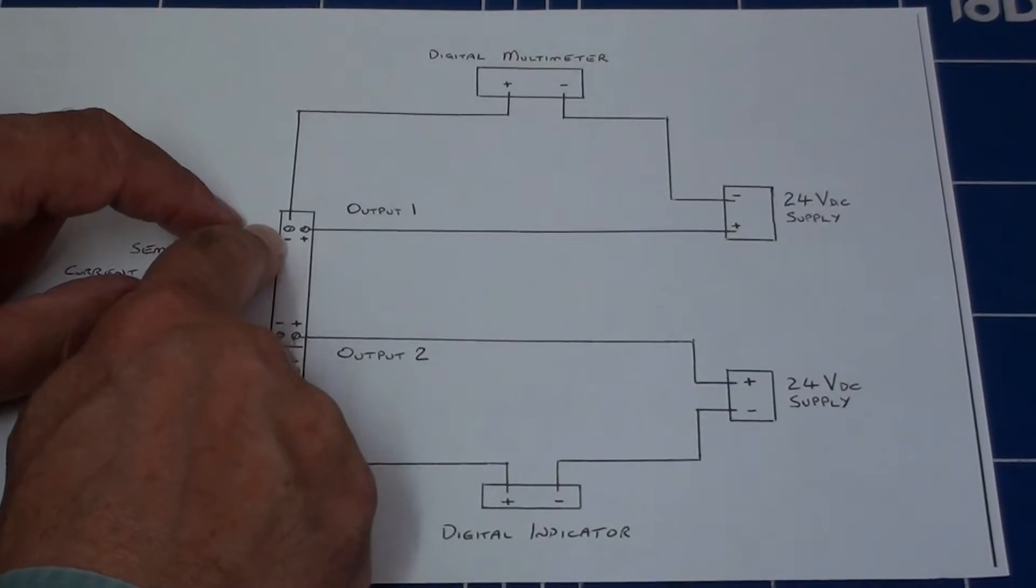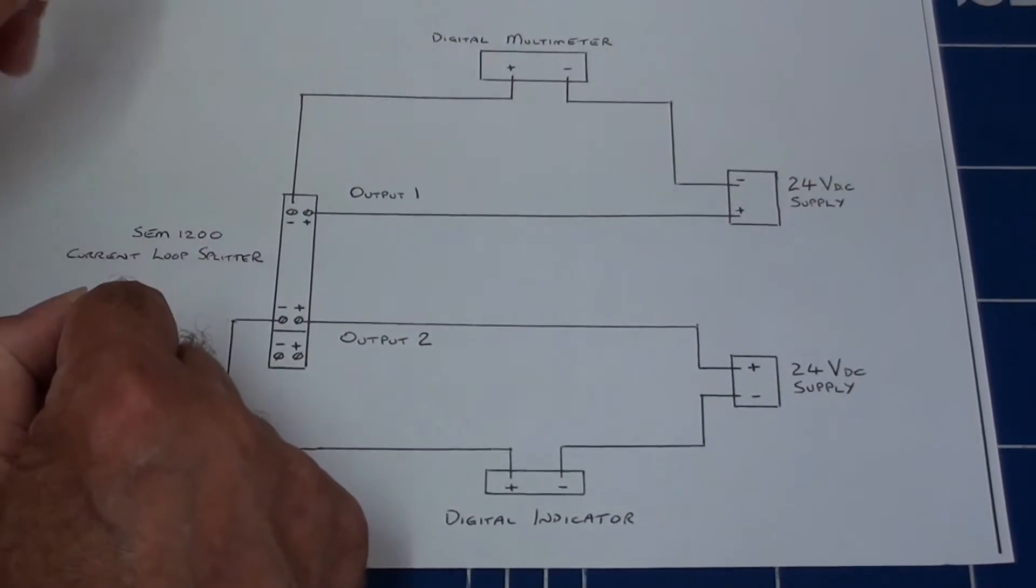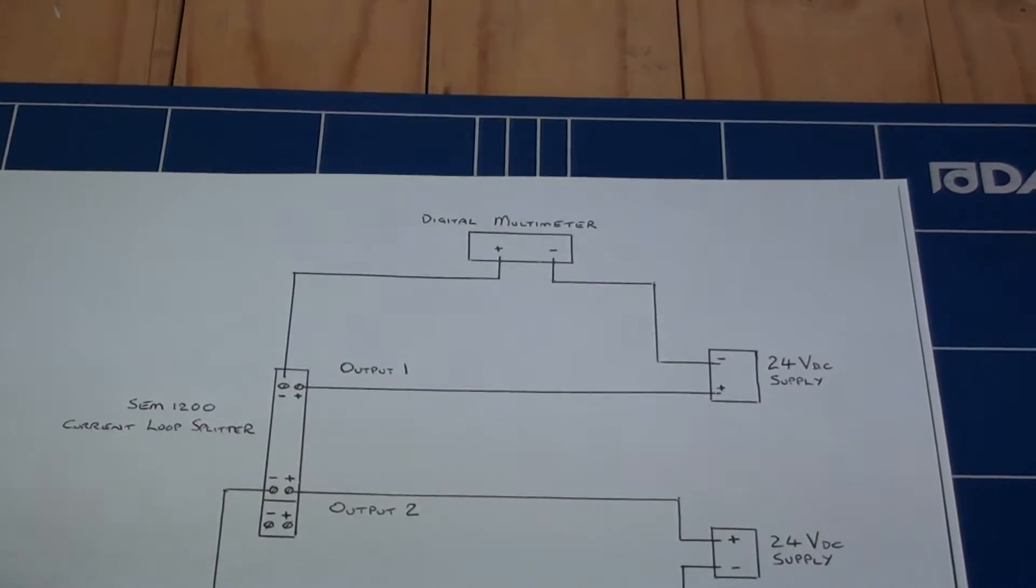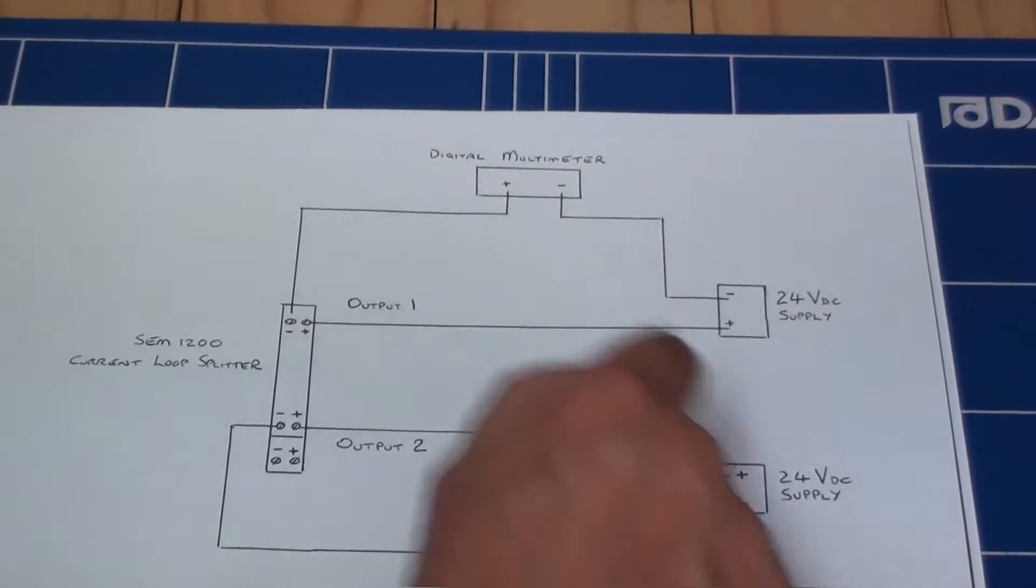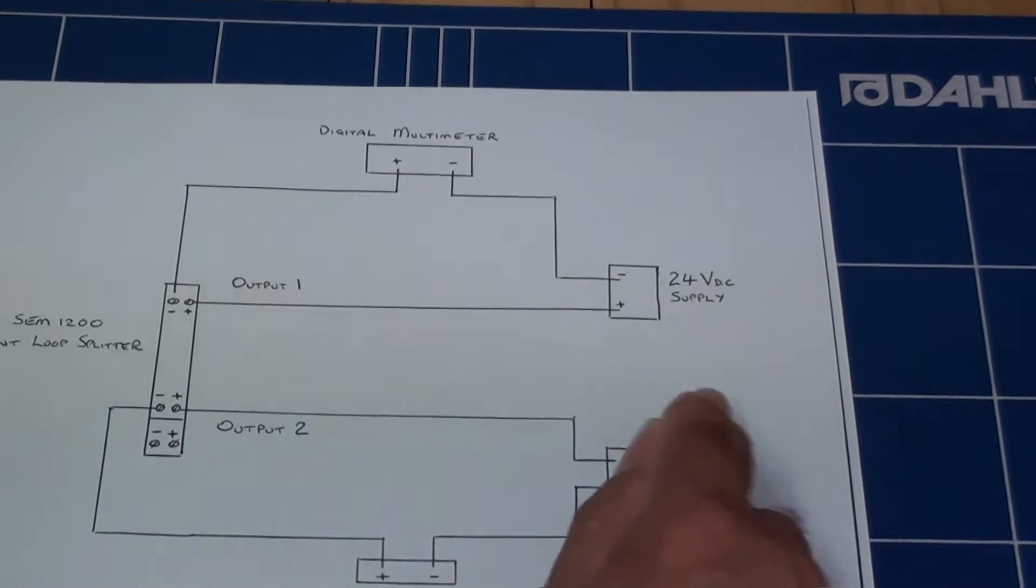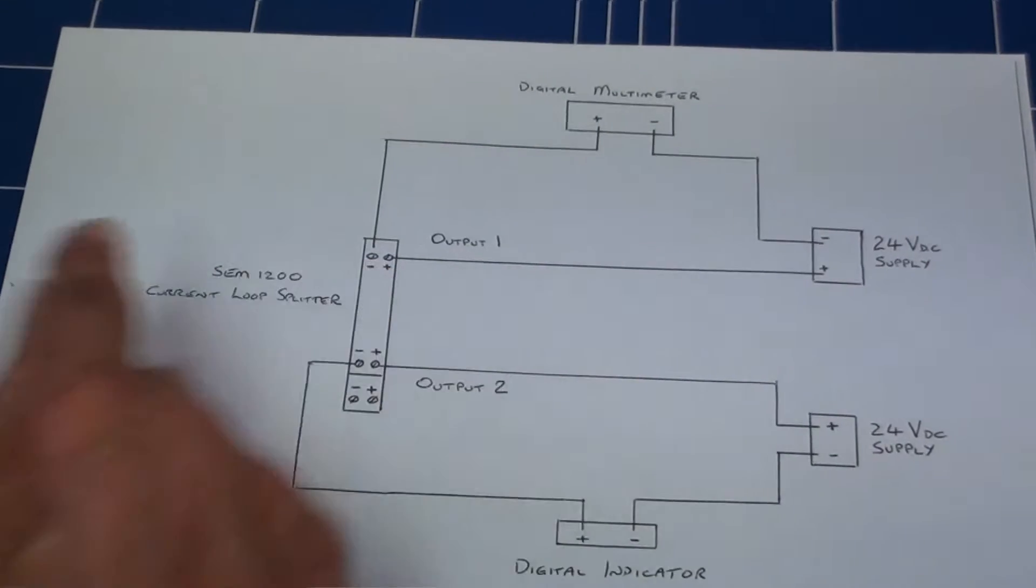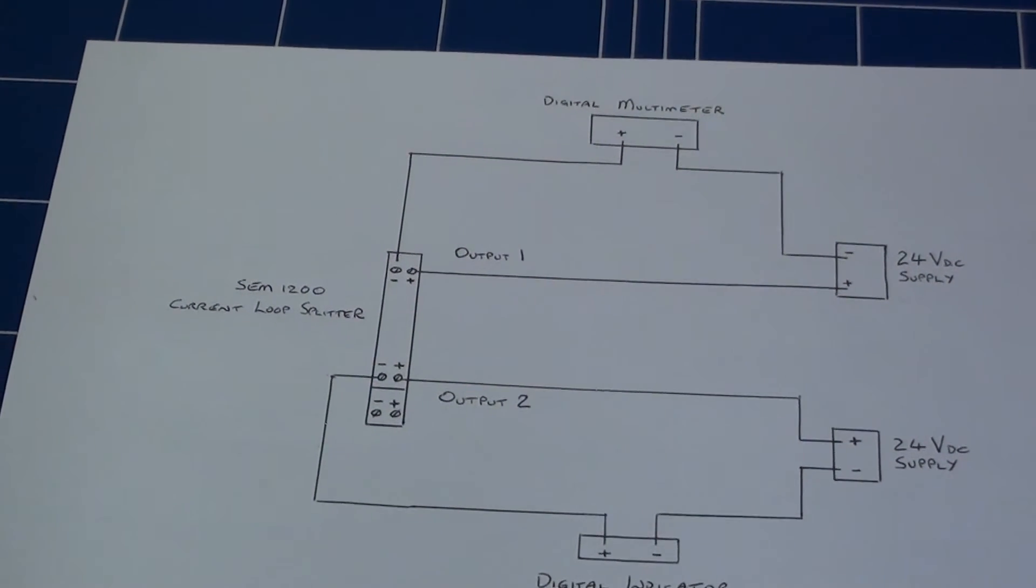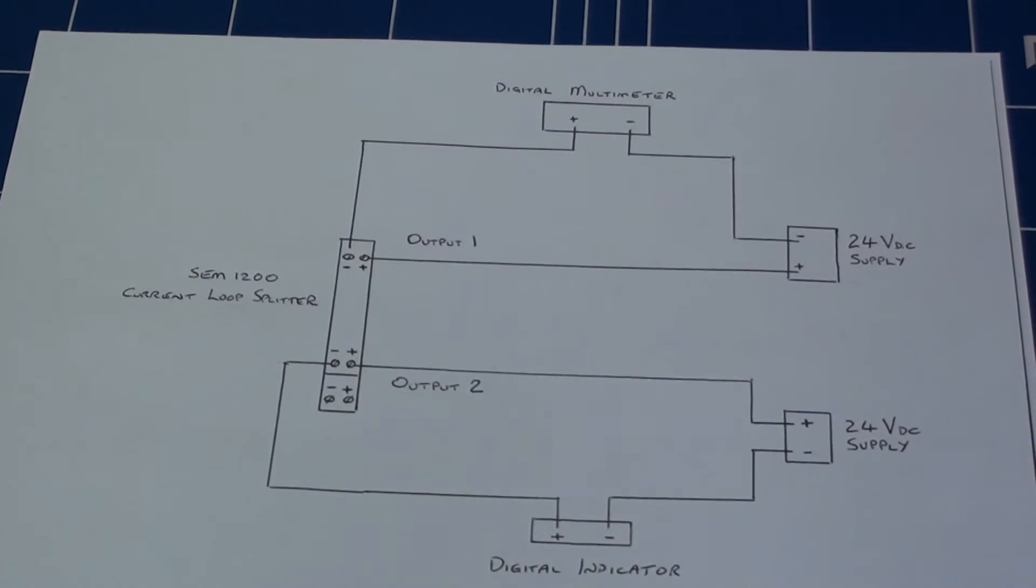On the SEM1200, minus from the output terminal on output 1, for example, goes to the plus on the multimeter. The minus from the multimeter is connected to the negative of the 24V DC supply, and the plus of the 24V DC supply comes back to the plus terminal on output 1 on the SEM1200.